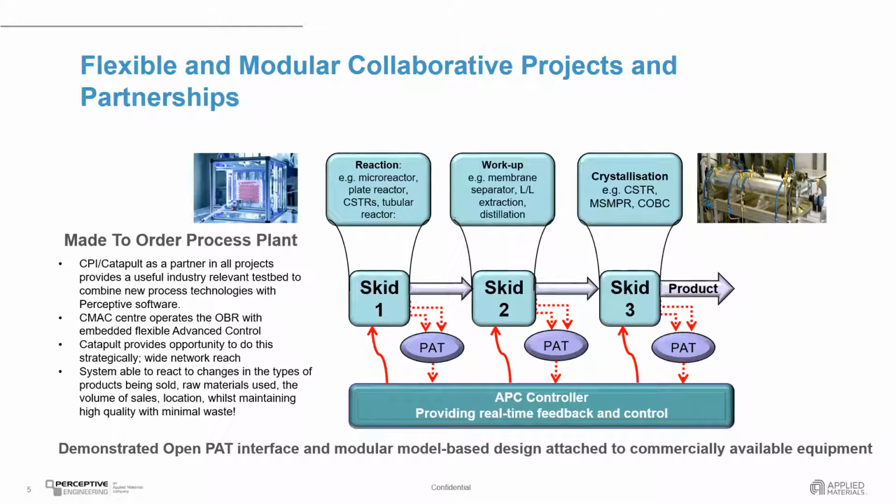Were we able to really enhance the precision of control and safety of these units, particularly with the continuous oscillatory flow reactor? It's quite a complex system with something like 15 or 20 temperature measurements along the snaking reactor, and then we were measuring particle size at multiple points with FBRMs, and integrating this PAT in, at the time, in as modular a way as we could, using OPC UA, but the standards weren't that well developed. So this was about 8 or 9 years ago.